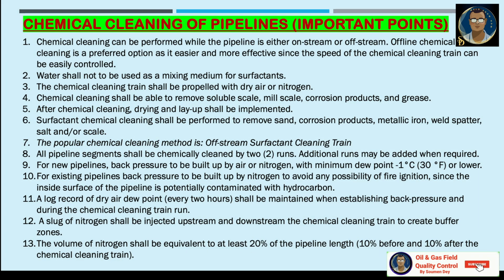Now some important points to discuss in relation with chemical cleaning of pipeline. Chemical cleaning can be performed while the pipeline is either on stream or off stream. Offline chemical cleaning is the preferred option as it is easier and most effective, since the speed of the chemical cleaning train can be easily controlled. Water shall not be used as a mixing medium for surfactants. The chemical cleaning train shall be propelled with dry air or nitrogen. The chemical cleaning shall be able to remove soluble scale, mill scale, corrosion products and grease. After chemical cleaning, drying and layup shall be implemented.